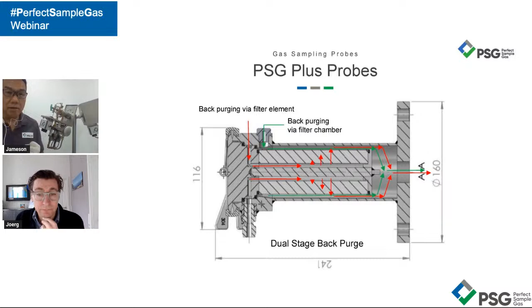It also varies slightly depending on the country. So in view of this, when we design the sample probe, we have to consider the head space. The head space plays a very important part. Imagine if you have a big head space, how much sample or how much calibration gas has to be refreshed? So they get a good sample representative to the gas analyzer.